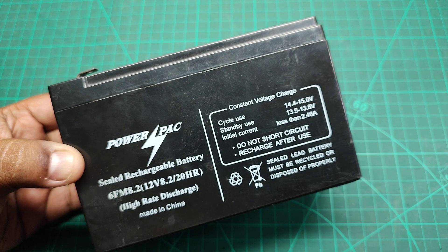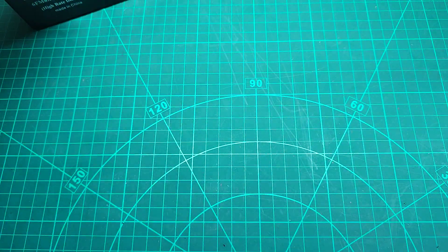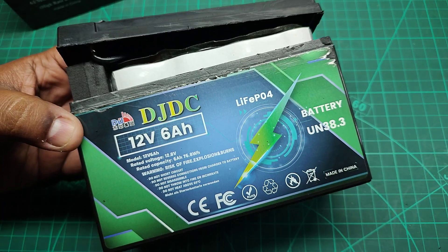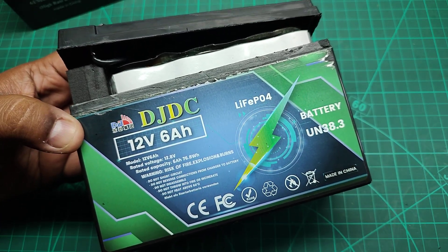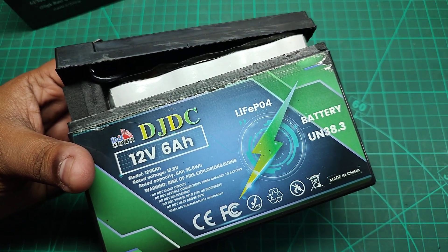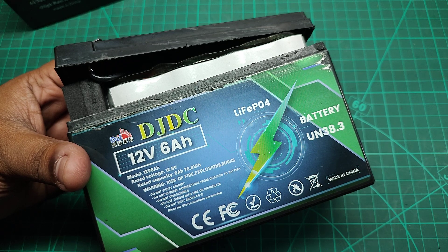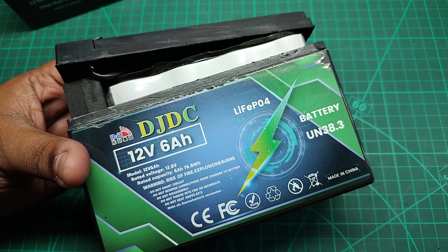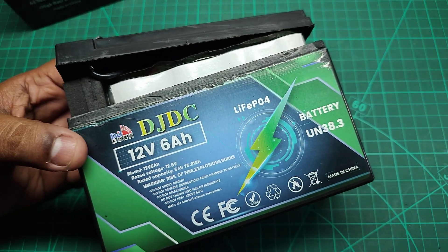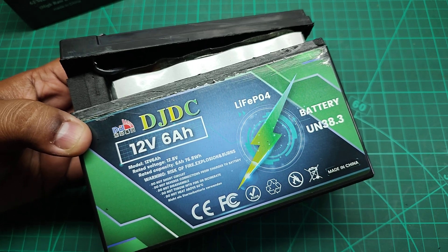The issue with this kind of battery is they don't last much longer — in my experience one to two years maximum. Now I'm replacing it with this battery: it's a lithium iron phosphate battery, the latest technology right now. The only downside is it has lower capacity, but lithium-ion batteries have much larger depth of discharge compared to lead acid, so 6 ampere-hours is not a big deal.